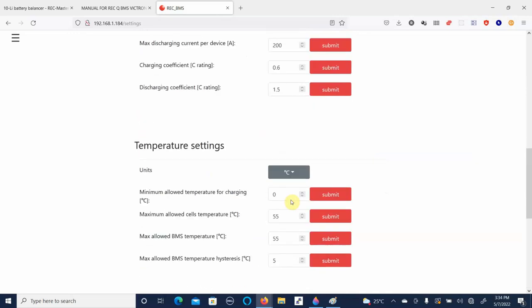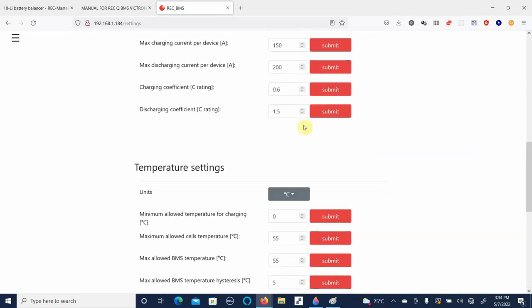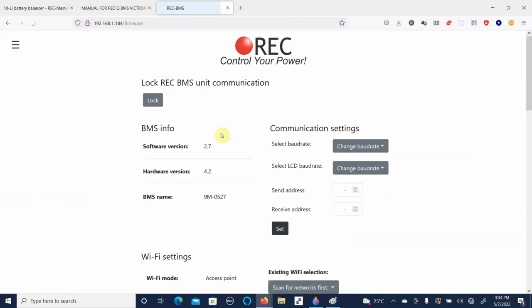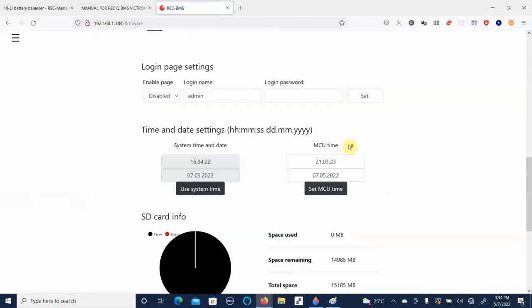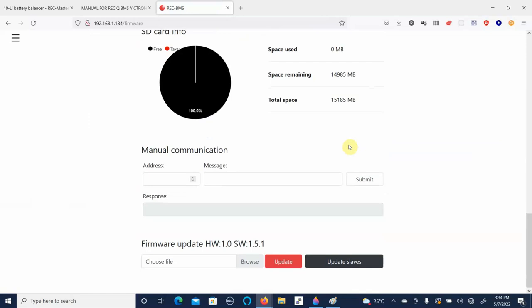Now there are some other parameters, second lower level parameters, that you may need to set, especially if you're connecting to a Victron system. So I'll show you how we do that now. We go into firmware and we scroll down to the bottom of the page, and we can see we have this manual communications section. This allows us to go in and manually set parameters without using the graphical interface.